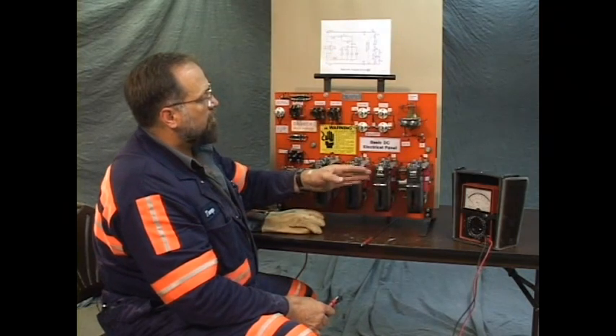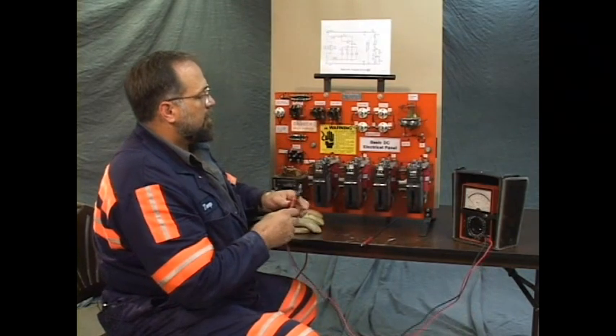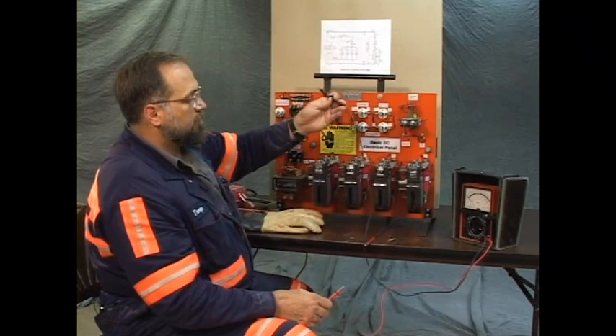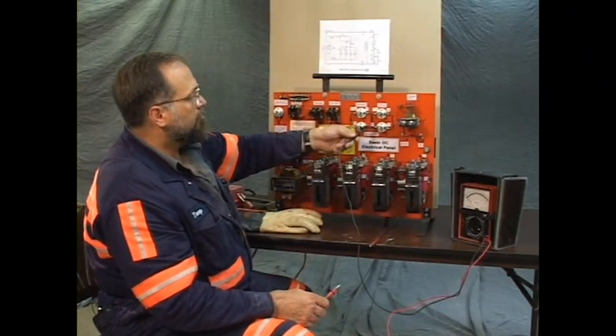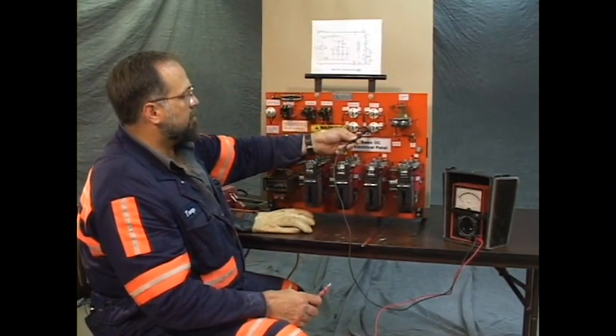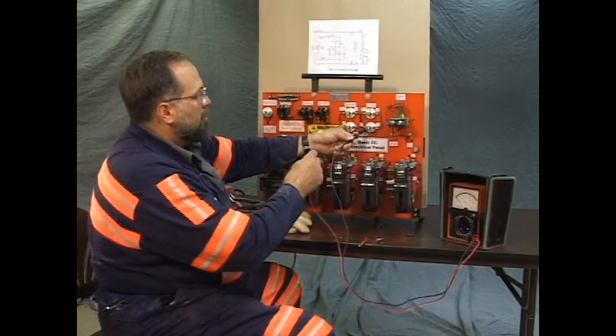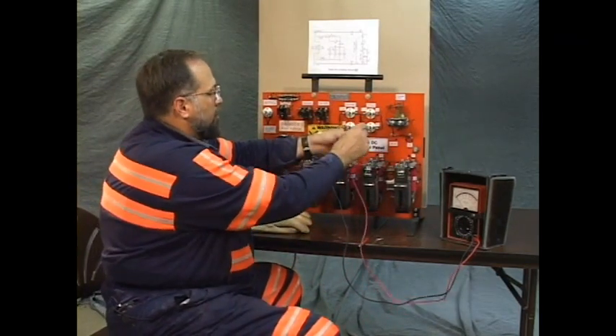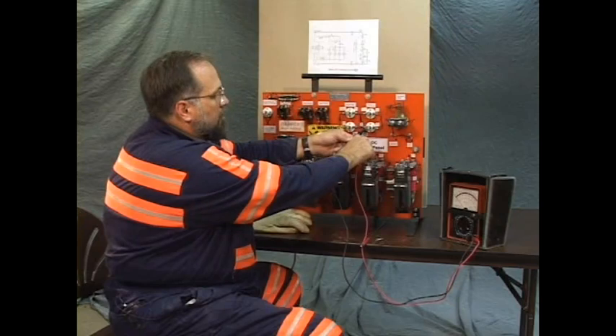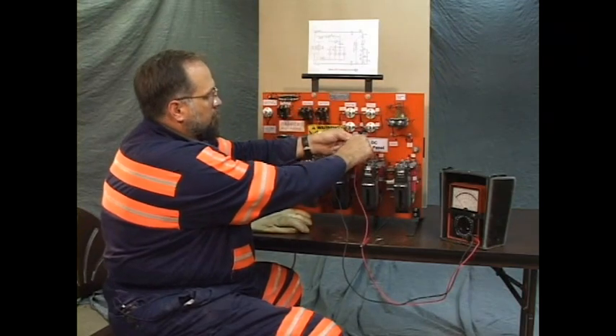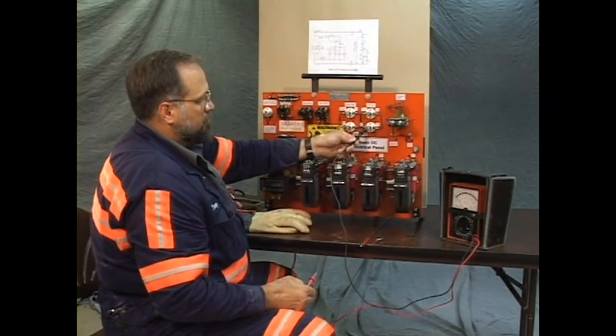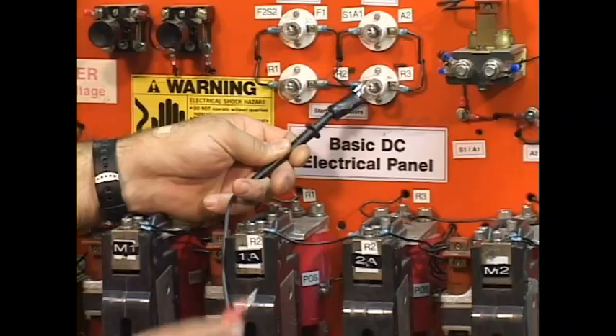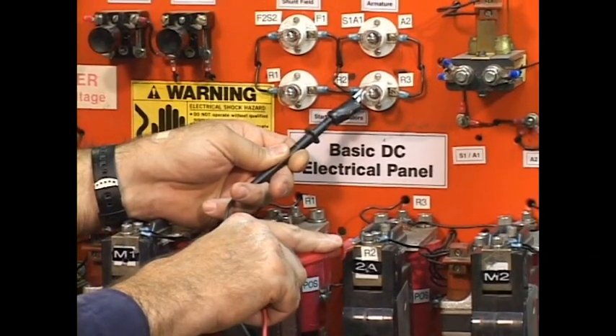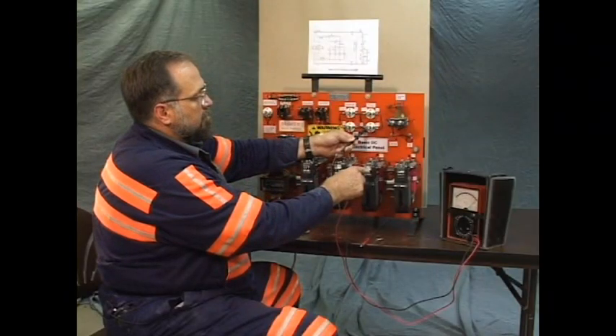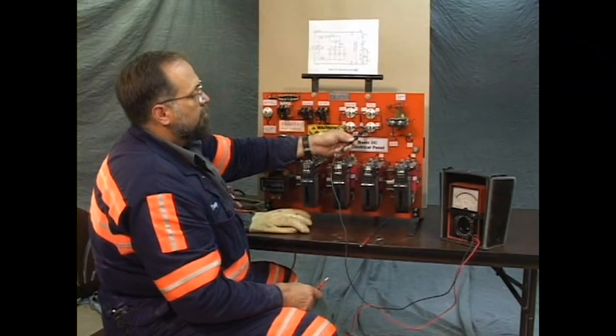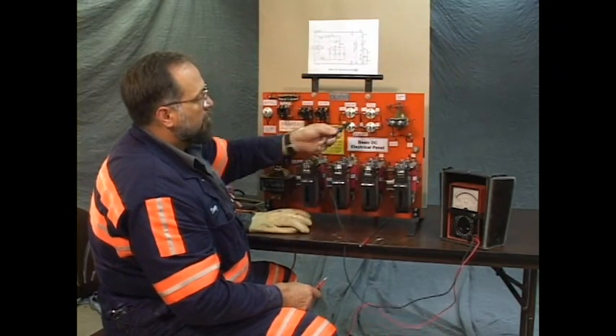I'm going to disregard the labels and just check this as if we don't know where it's supposed to be. I'm going to try to determine which side of this light is connected to which side of the contactor. I'm going from the R2 on the light. I'm going to ignore this label and see if it's to the back. It's not. So let's check the front. Hey, there it is. So we've oriented ourselves now. We know where we're at.